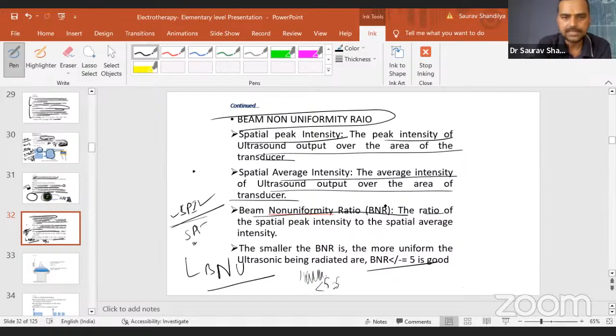It is very true that in your ultrasound head there is a transducer where one or two points will have more peak intensity, but other points will be around the average. So we take the peak divided by the average and work out that ratio. If that ratio is less than 5, the beam is going more uniform. Otherwise, one point is going more, other points are going less, and it will be non-uniform ultrasound activity, and this will work badly for you. The machine will not be good. So you should ask about all these things when you purchase the machine.